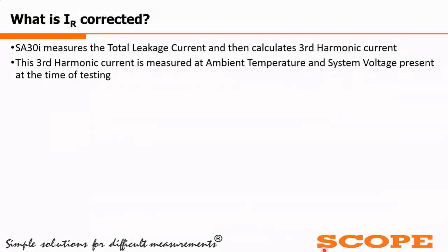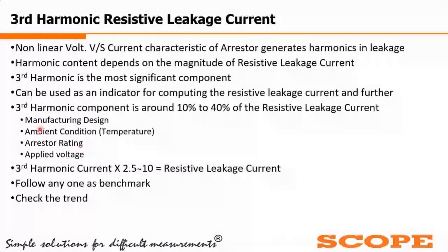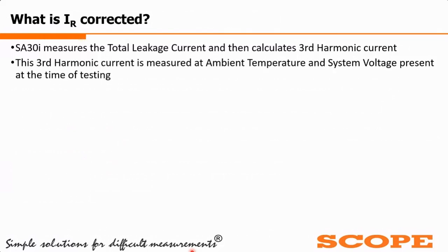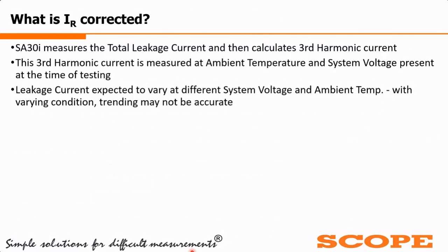Now, how to do the trending? Because here, as we have seen, it varies with the ambient condition, arrestor rating, and applied voltage. So I have to keep a standard value, that is the IR corrected. Now our product SA30i or SA30i plus measures the total leakage current and then calculates the third harmonic current. This third harmonic current is measured at the ambient temperature and whatever system voltage is present at the time of testing. So I need to go to a standard value.